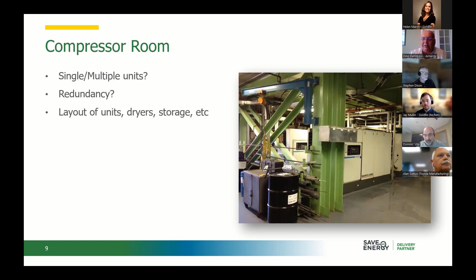And that really leads us into the next slide there, Jay, which is the controls, right? And how the compressors are actually being controlled against the load. I remember walking into one compressor room, and this was in an automotive parts manufacturing facility too, and they had 3 compressors running. It turned out at the end of the day, one of them was basically overcoming leaks, and one of them was, because of the control settings, simply on, never cycling off because of a transient event. After a little bit of work in that plant, they ended up with 1 compressor running basically all the time. So, Dino, anything to highlight here?